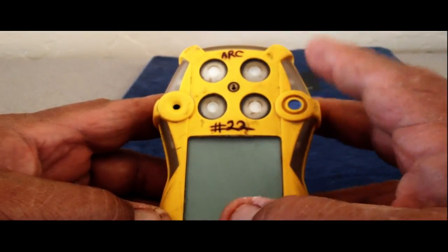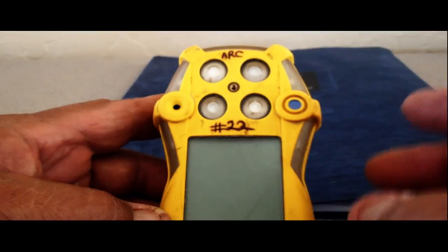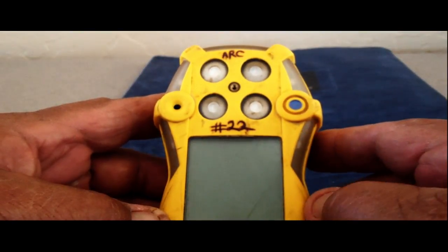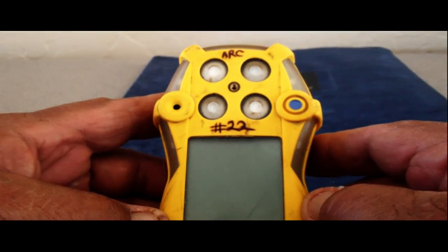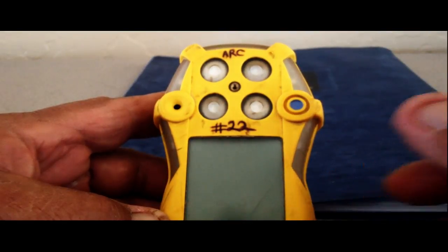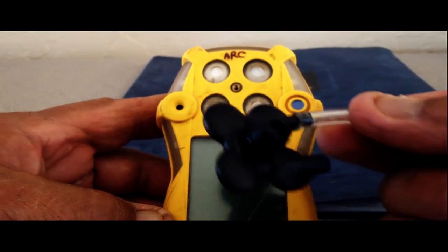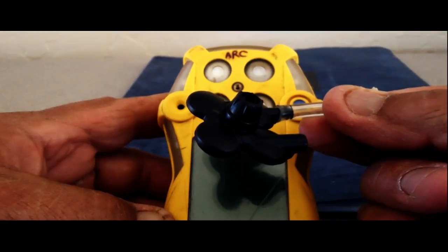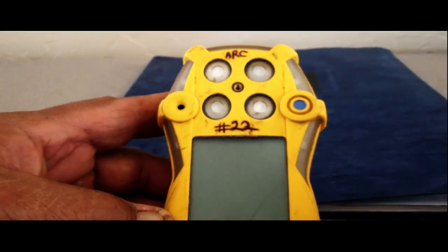When we calibrate this, because it is a diffusion type meter, we have to change regulators. The demand regulator will not work. You have to use an on-off regulator. And it has a different calibration cap that you have to use with it. So we'll go through that process here in just a second.